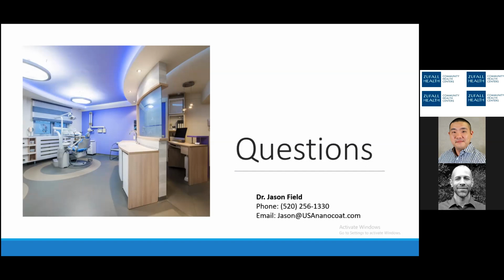And just a quick note, when comparing other units, I would make sure that the bulbs themselves are rated for about 25,000 hours. Many manufacturers use bulbs that maybe last for 8 to 12,000 hours, and even from day one, the intensity of those UVC bulbs is probably not as high as it needs to be.